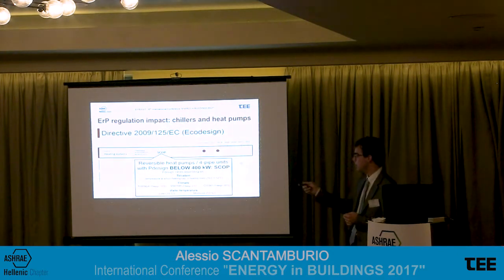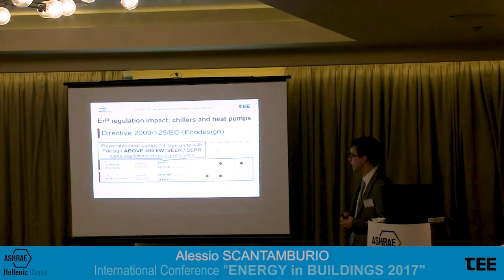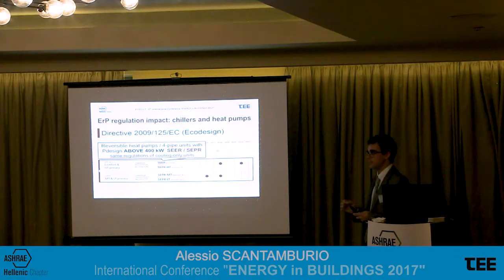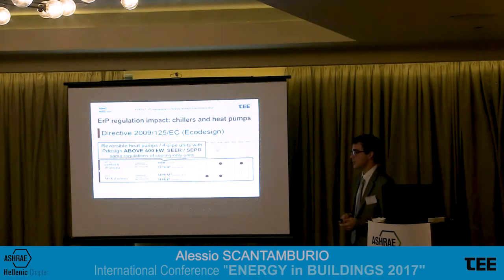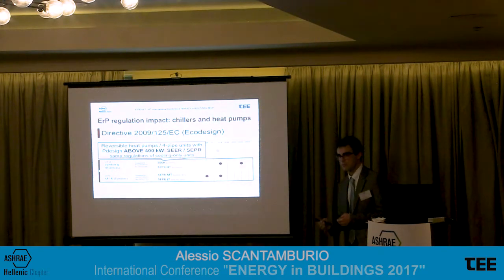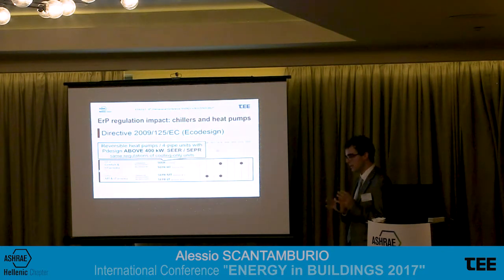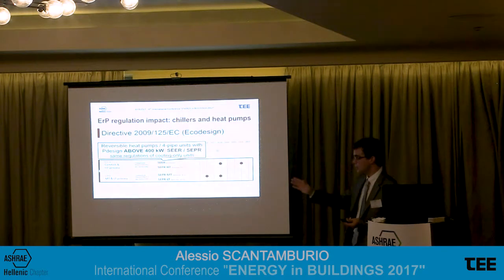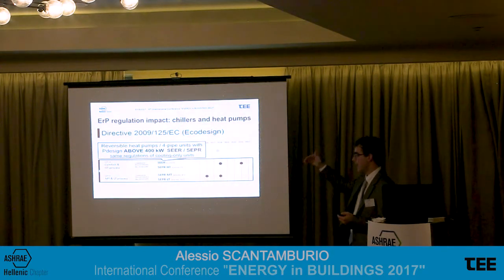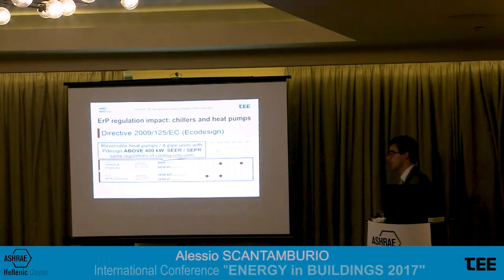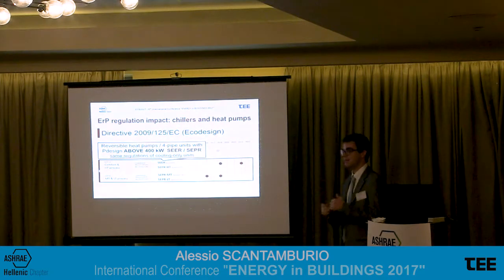If this design power is below 400 kilowatts, then it must be compliant with the SCOP. And if it is higher than 400 kilowatts, well, it must be compliant with the parameters of a cooling-only unit. And it is not so fair, in our opinion, because a unit which is intended to produce hot water can be as efficient as a unit intended to produce only cold water. Okay, but this is the regulation, and we must be compliant with this one. So in this particular field of the market, reversible units, this means heat pumps and 4-pipe units above 400 kilowatts of heating capacity at design condition, must have the same efficiency levels of a chiller. And it is quite tough.